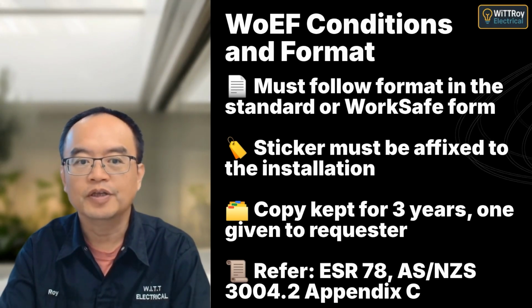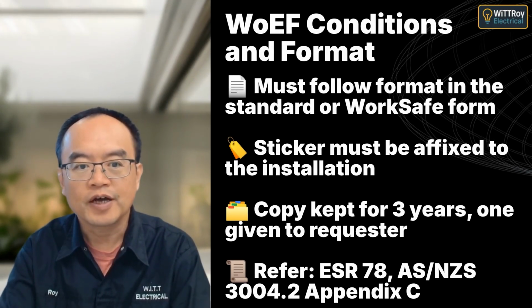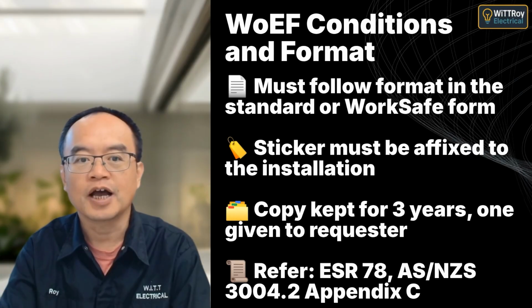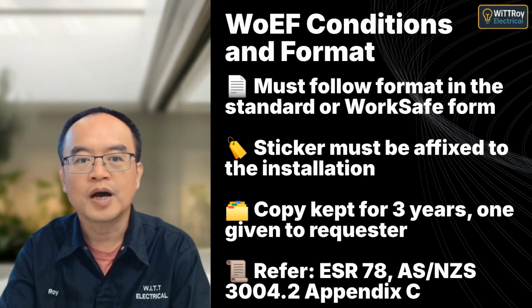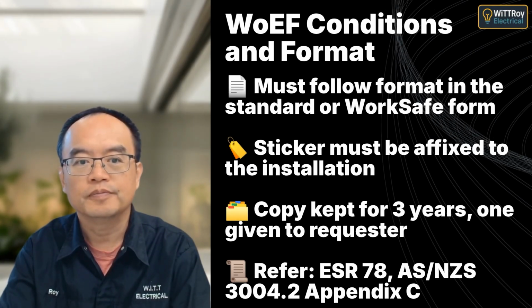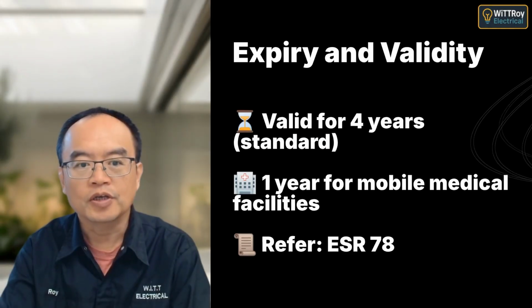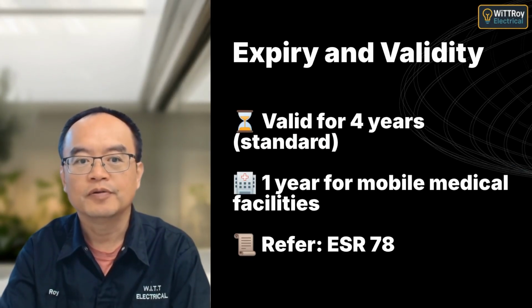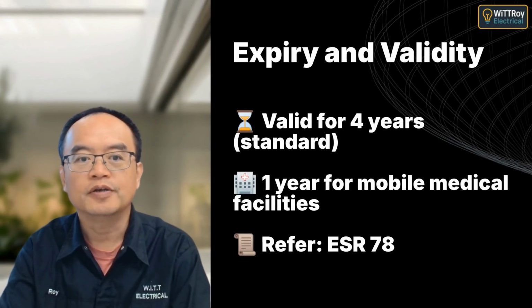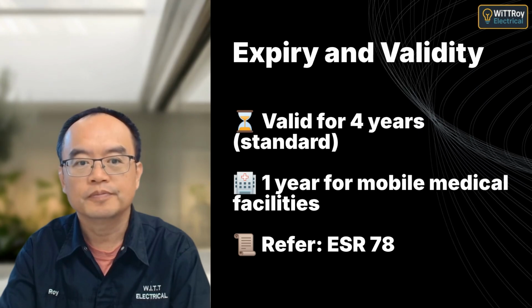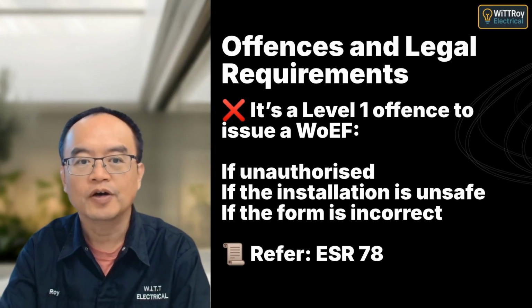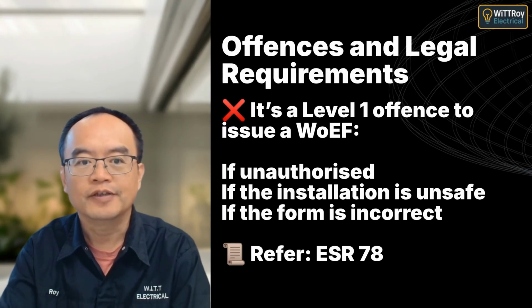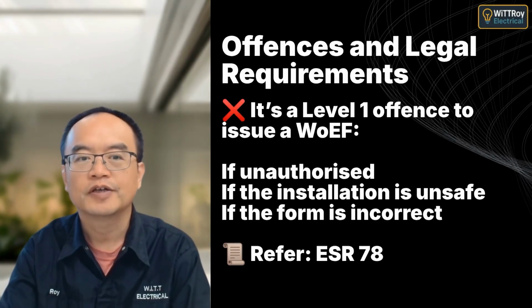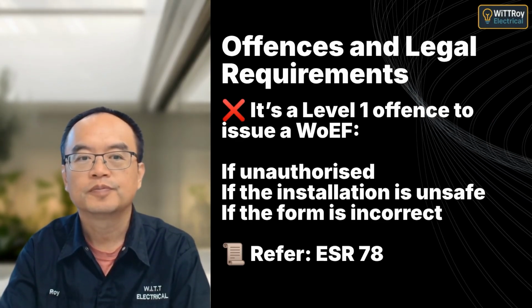The WOEF must be completed using the correct form, affixed visibly to the installation, and copies must be kept and provided as required. A WOEF usually lasts 4 years, but for mobile medical facilities it's only valid for 1 year. Issuing a WOEF when you're not authorized or for an unsafe installation is a level 1 offense and could result in prosecution.